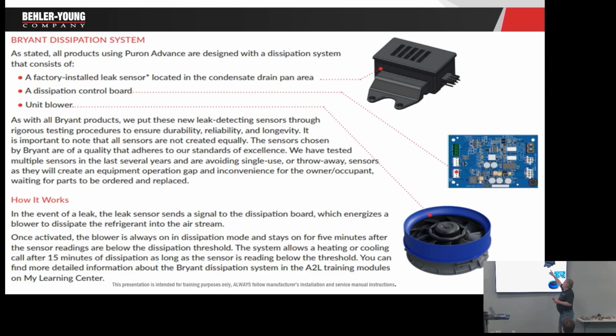So everything with an evaporator will have a sensor in it, okay, and it's looking for R32 from what I'm told. So propane, butane should not set it off. Other chemicals aren't supposed to set it off. So it's set at about 20% of the lower flammability limit. So the lower flammability limit of 454B is about 12%. So it's looking for 20% of that 12%. So it's a very, very small amount.